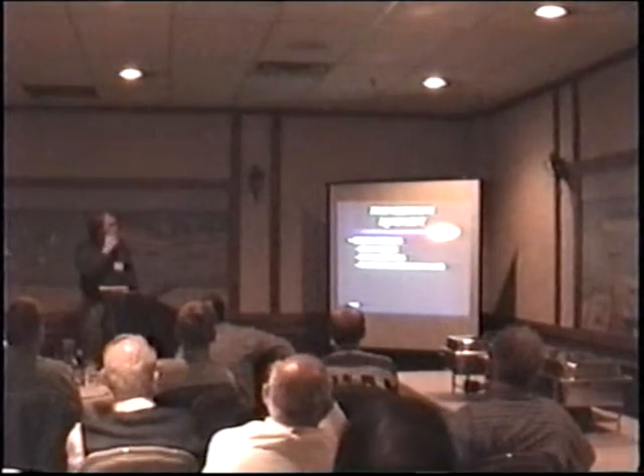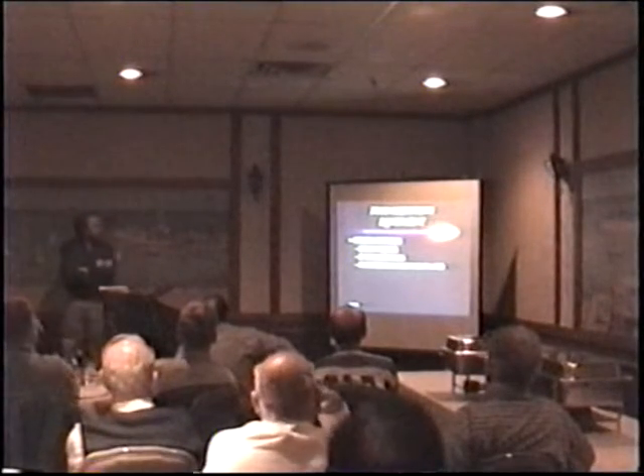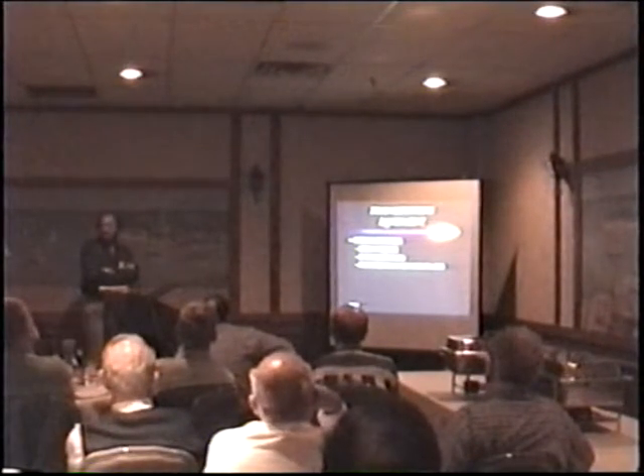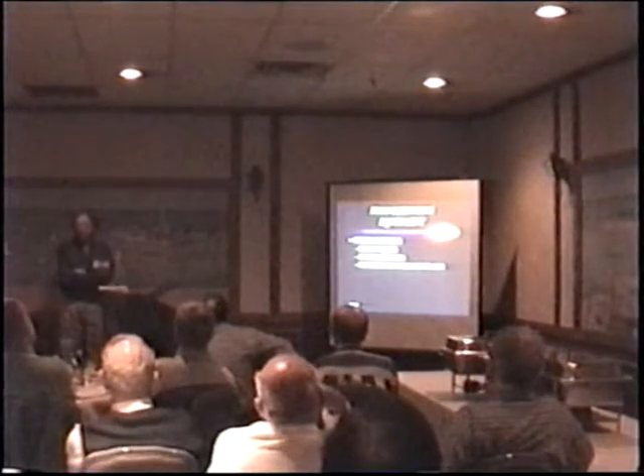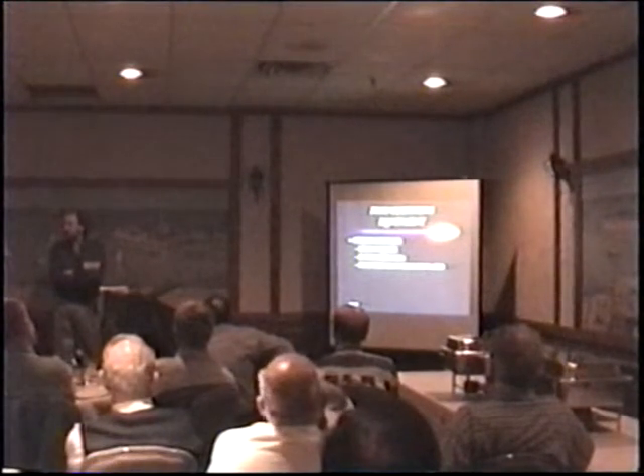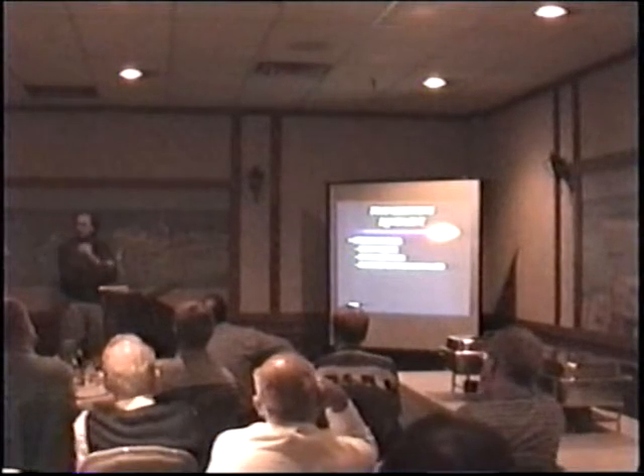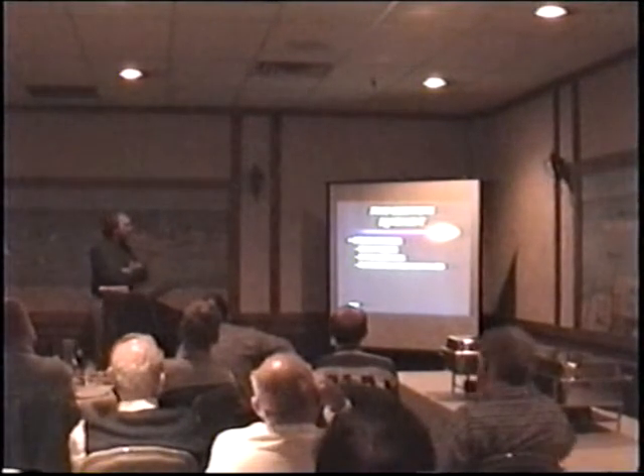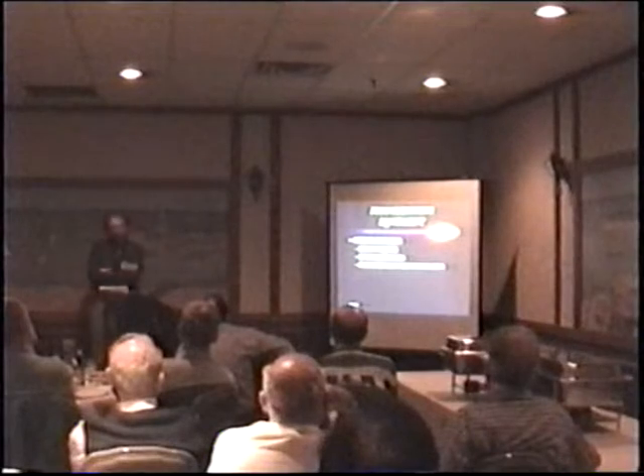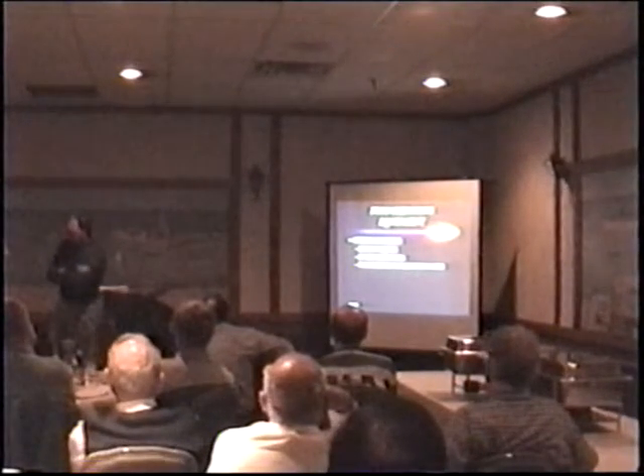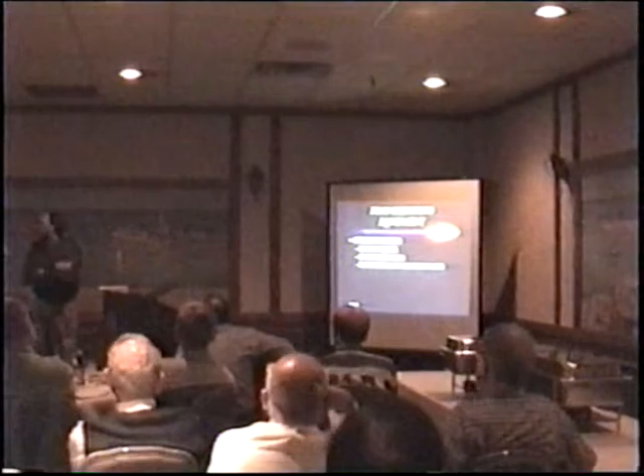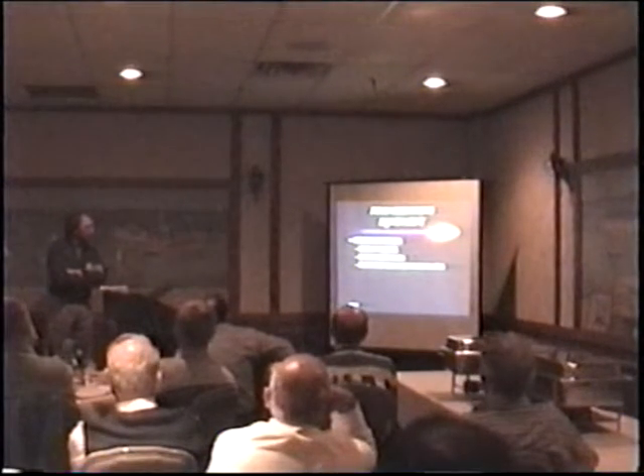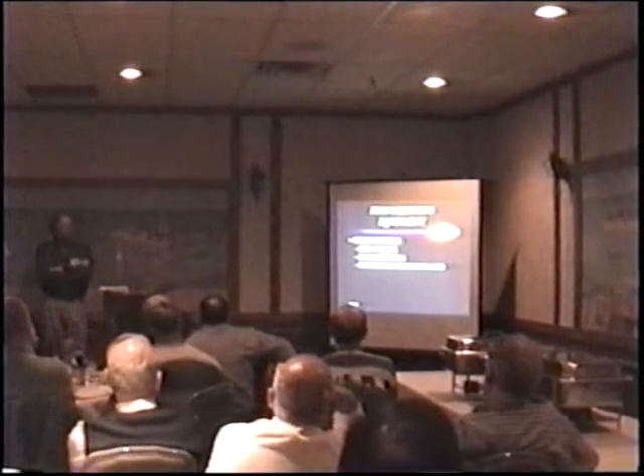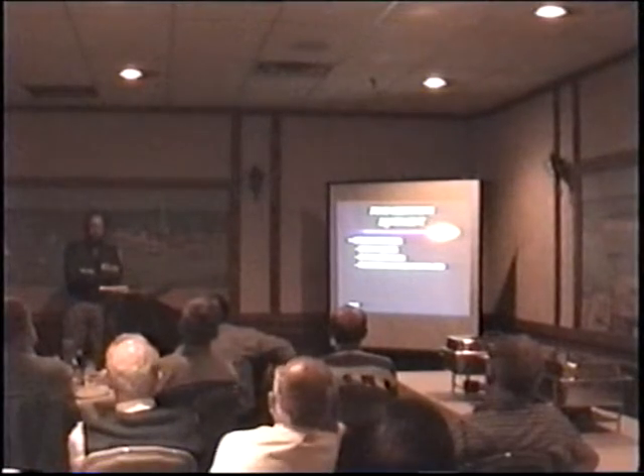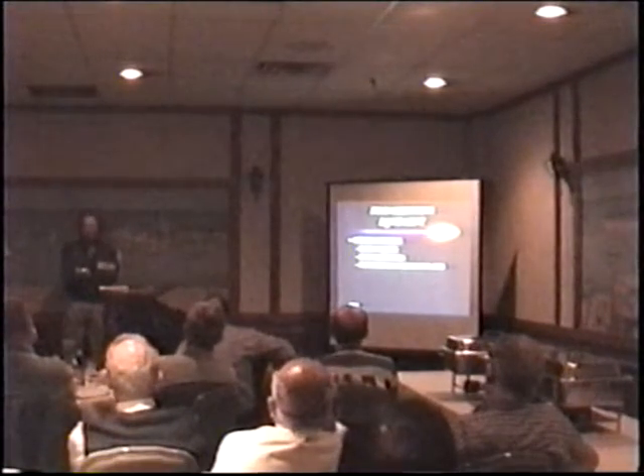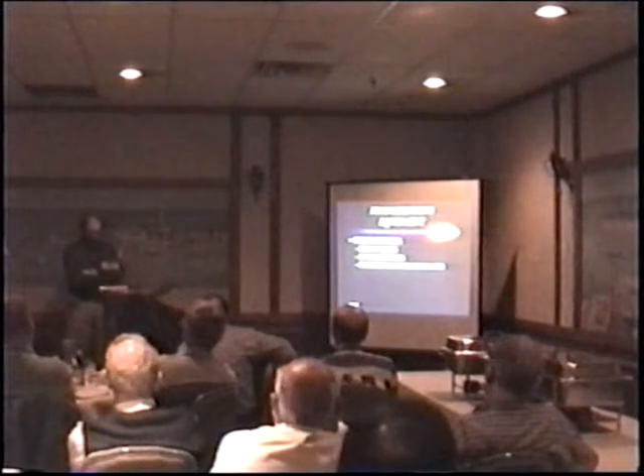So, other methods of proportioning, these are some older ones. Direct orifice was used in the old days on the old deluge systems. They know what their water flow is going to be, they know what their concentrate pump will be, they just shoot it in there, pre-sized orifice plate. Inline inductors are not a good way to go for systems because their pressure loss is so high with the inductor. And pressure proportioning tanks, again, these are kind of used with protein foam. We've made a few of these for use at some ADM facilities in Cato and down in Iowa.